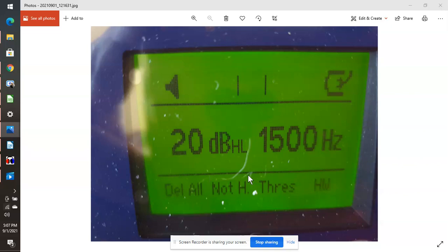If you're testing manually, then you can write them down or you can save it to the software program. There's a basic software program that comes with the audiometer. The more comprehensive program is Workplace Audiometry, and that's what we tend to use in Australia because it does all the reports and all the references and percentages of hearing loss for each different state, as they're all different, unfortunately. So it's a very simple process.